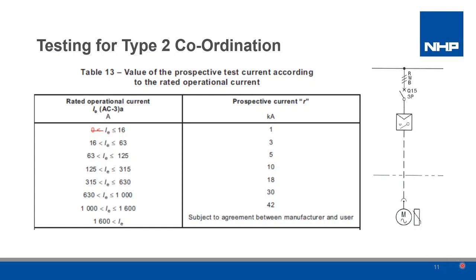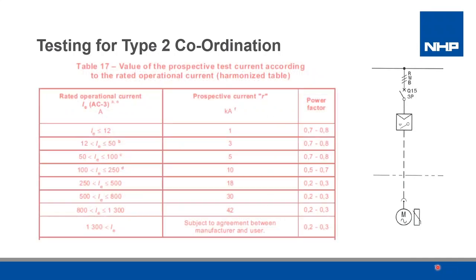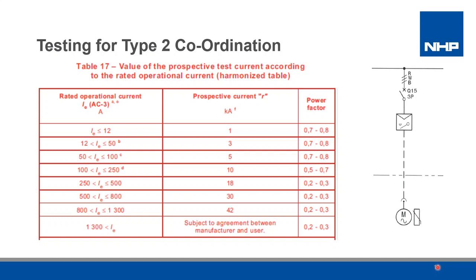The R value, with the release of the 2015 standard update, Table 13 is maintained. However, Table 17 has been added to define the R testing fault levels for the starters. The R value for a starter up to 12 amps is 1 kA, whereas a starter between 500 to 800 amps has an R value test level of 30 kA. Table 17 is a harmonized table to provide commonality for IEC and North American market UL testing requirements.